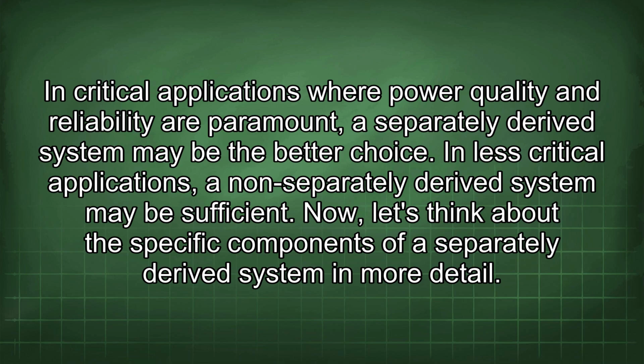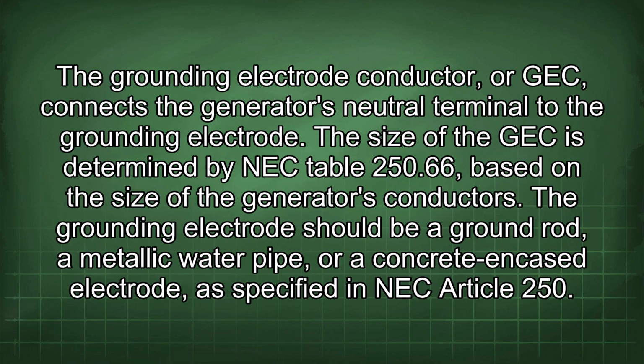Now, let's think about the specific components of a separately derived system in more detail. The grounding electrode conductor, or GEC, connects the generator's neutral terminal to the grounding electrode. The size of the GEC is determined by NEC Table 250.66 based on the size of the generator's conductors.